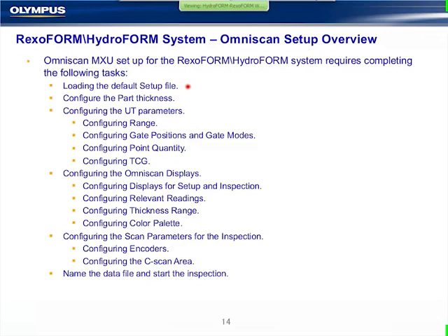So after loading that file, we will enter the part thickness for what we're going to inspect. We will adjust our UT parameters, including configuring the range. Probably the most common mistakes customers make, when we're looking at data, are improper range, meaning mostly it's way too long, and improper gate position and gate logic. We'll talk a little more about those when we get to that. The point quantity of the A-scan is very important, and we will configure a TCG manually, not using the wizards. Then we will configure our displays, relevant readings, the thickness range for our statistics, the color palette of the C-scan, and then we will configure our scan parameters, name the file, and do the inspection. So it's a fairly short process compared to a typical phased array weld inspection from scratch and calibrations.